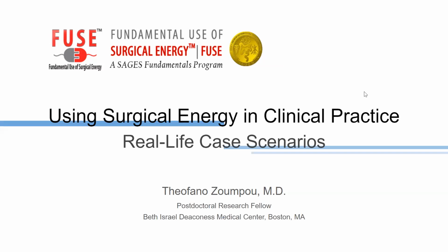You're going to generate really high temperature. That's the highest temperatures when you do that, when you arc it over, right? When you hold it half a millimeter away from the tissue, you generate heat. And then there's desiccation when you actually stick the active electrode into the tissue or onto the tissue. You generate less heat, but potentially you get a better hemostasis to deeper structures that way.